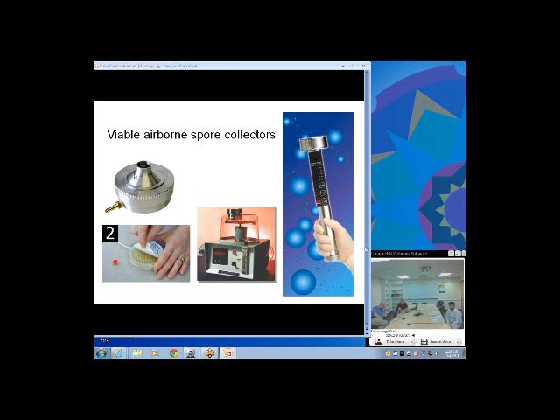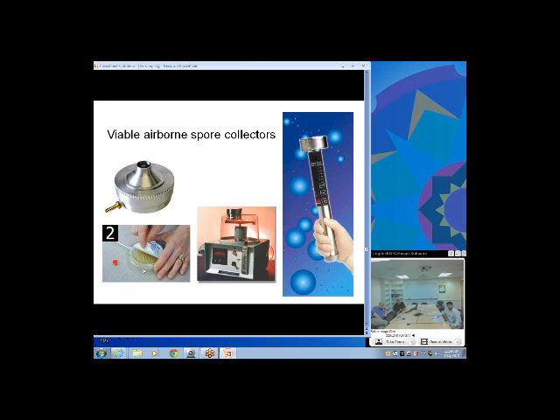For viable collectors, air is pulled in the top through approximately 450 small holes. Inside, an agar plate is mounted so spores impact into the agar. The plate is covered and incubated under the hood for a couple of days so it doesn't dry out. You then count how many colonies grew, and by examining the colonies under the microscope you can identify at least the genus — sometimes down to species level for common organisms.